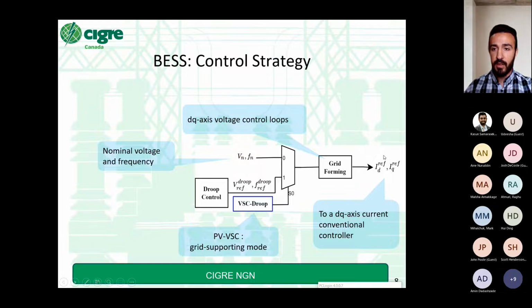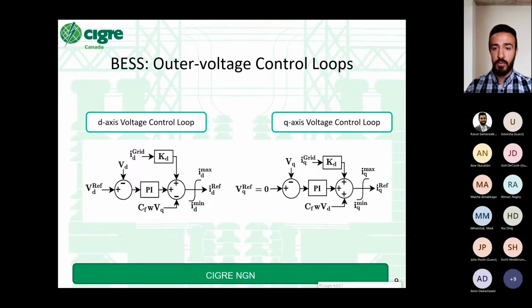This grid forming is going to generate the ID reference and IQ reference for the D and Q axis current conventional controller. This is the battery energy storage outer voltage control loops. Looking here, by giving VQ0, the voltage vector is going to be oriented with the D axis. Therefore, the regulation of VD is going to be adequate in controlling the AC voltage magnitude. The incorporation of the CF omega VQ and CF omega VD is going to reduce the coupling on the outer voltage control loops. Also, the D and the Q axis current of the grid is incorporated to reduce the effect of load dynamics on the voltage control tasks.